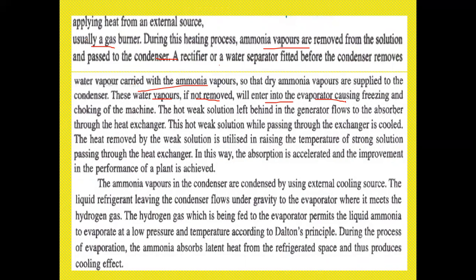The hot weak solution left behind in the generator flows to the absorber through the heat exchanger. Now, this hot weak solution while passing through the exchanger is cooled. The heat removed from the weak solution is utilized in raising the temperature of the strong solution passing through the heat exchanger. So that's why the absorption is accelerated and the improvement in the performance of the plant is achieved.